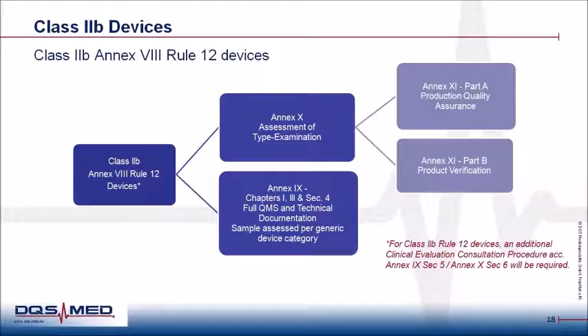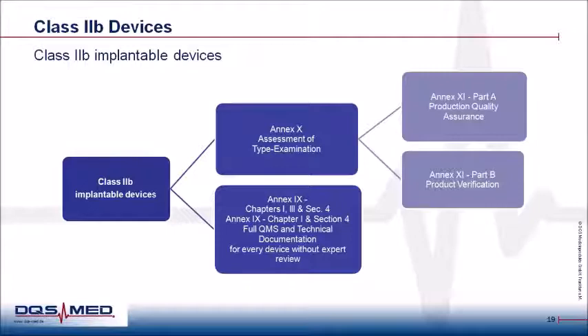Class 2B implantable devices, the conformity assessment route remains the same. That is either Annex 9, including chapters 1, 3, and section 4, or Annex 10 along with Annex 11 Part A or Part B. Here, the only difference is when assessing the technical documentation for Class 2B implantable devices, no sampling is carried out and all the devices must be reviewed.